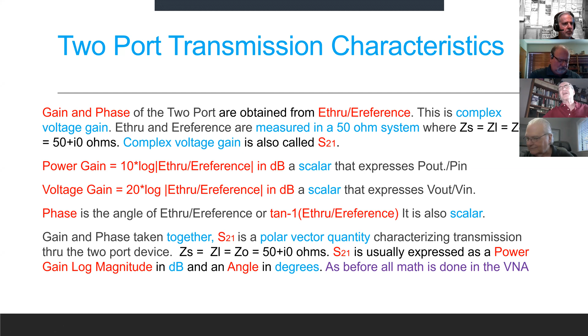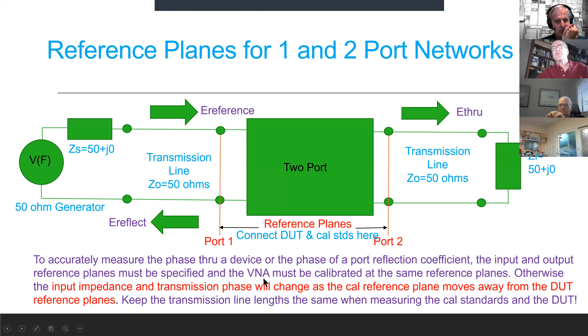Well, the last thing that we need to cover are reference planes. So here's a 2-port, and the reference planes just happen to be at these 2 red lines. And you need to connect the 2-port, which is the device under test, and the Cal standards at the 2 sets of reference planes. Why? Because if you calibrated the device at this reference plane and measured the device here, the phase would be different, which would upset the input impedance and also the transmission phase through the device. So it's very important when you're measuring something to understand where the instrument is calibrated and where you're actually making the measurement, which is where it was calibrated.